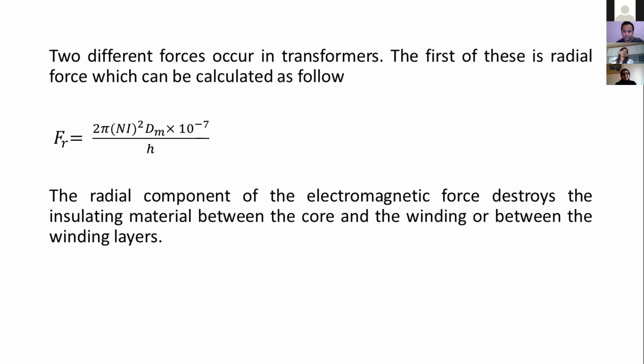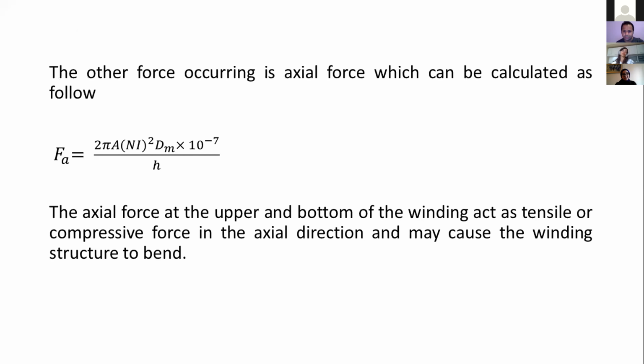Two different forces occur in the transformer. The first of these is the radial force, which can be calculated with the formula below. The radial component of the electromagnetic force destroys the insulating material between the core and winding, or between the winding layers. The other force occurring is the axial force, which can be calculated with the equation below. The axial force at the upper and bottom of the winding acts as a tensile or compressive force in the axial direction and may cause the winding structure to bend.